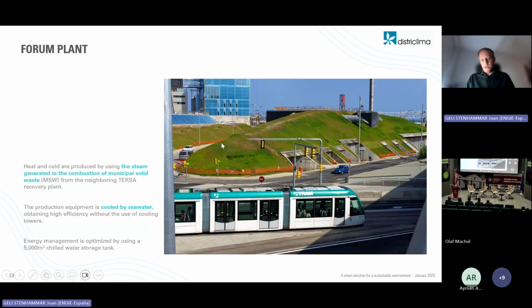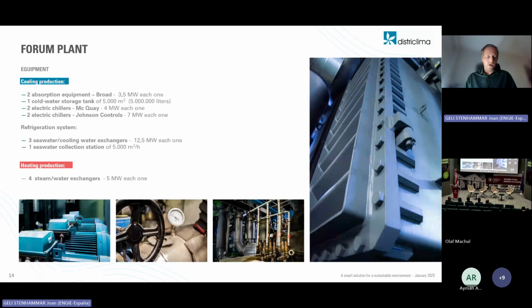Now, the first plant, which was built in 2004, is the Forum plant, built below this artificial hill, as you see. We have an important cold-water storage tank, this black box that you can see that pops out. It's a 12-meter high tank with 5,000 cubic meters. This allows us to accumulate roughly 40 megawatt hours. The equipment we have is 2 absorption chillers that can use the excess heat not used during summer, coming from the waste treatment facility. And then we have the chillers that are condensed with seawater. Finally, heating is produced with 4 steam and hot water heat exchangers.